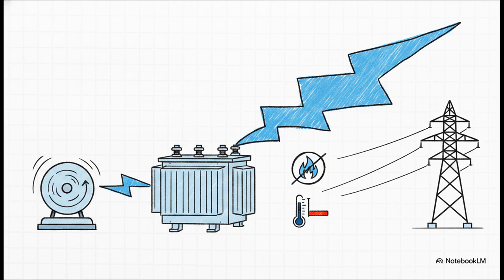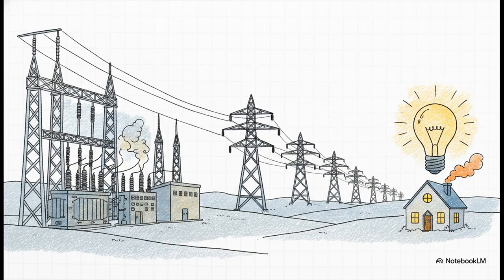Well, drastically increasing the voltage reduces the current, which in turn minimizes what engineers call I²R losses, which is basically just power lost as heat over those long-distance transmission lines. Next up is the switchyard. This area handles the switching, protection, metering, and overall control of all this heavy-duty electrical equipment.